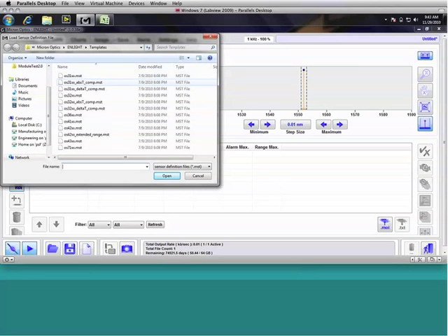You'll also see different permutations here for an OS3100, for example, where it can be compensated by an absolute temperature or a delta T or a relative temperature. And so it's important to know when we're establishing our system and building our sensors what our source of temperature compensation information is going to be.